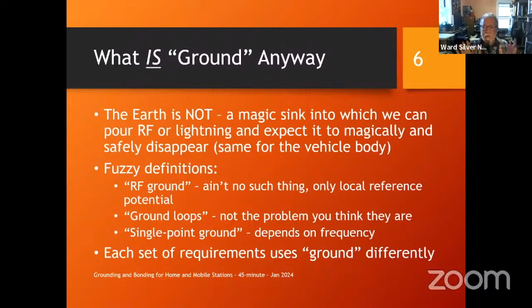Yes, that's good. But when you go and look up the bonding definition, all it is, is a connection intended to keep 2 points together at the same voltage. The key concept for bonding is that everything that's bonded together goes up and down at the same time. It goes up and down together. It's like a floating dock. All the dock and the boats go up and down together when a big wave comes along. And it's the same thing in electrical bonding. You want all of the bonded stuff to go up and down together.